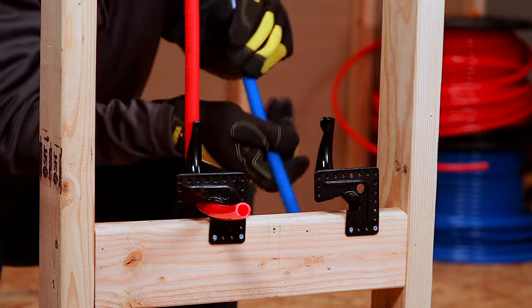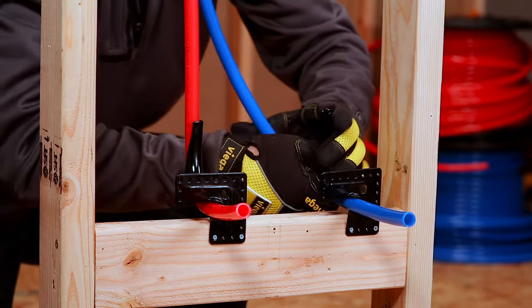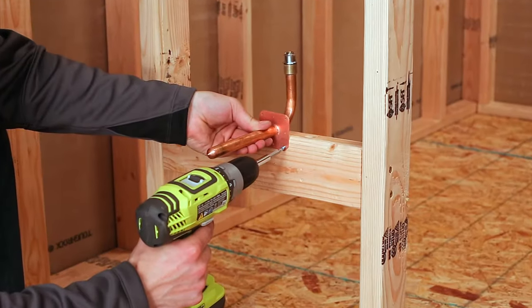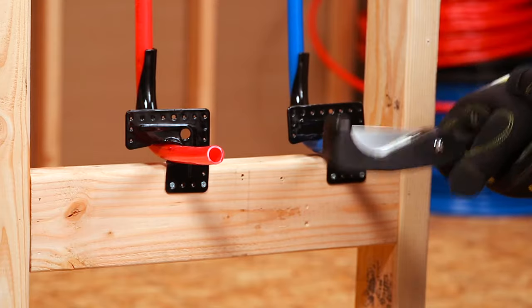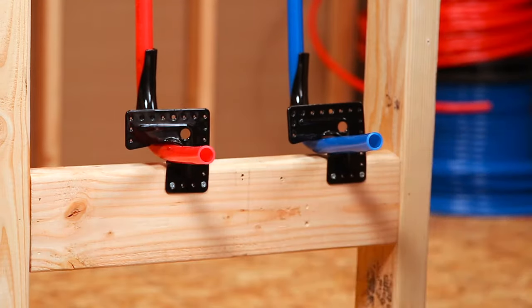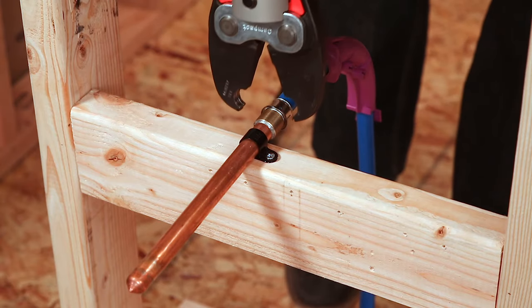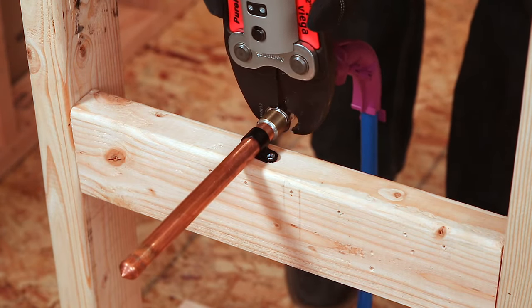For PEX, use either a bend support or an elbow to make the tight radius 90-degree turn. For bend stubouts with a flange, secure the flange to the wood via wood screws. Trim the PEX to the appropriate length, leaving some slack for expansion or contraction. Connect the PEX tubing to the PureFlow press connection available on Viega's copper stubouts.